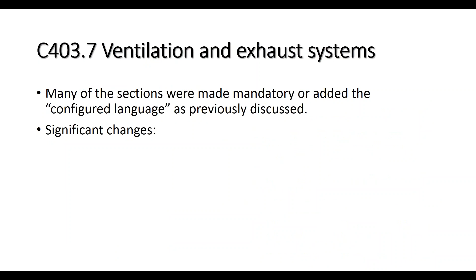Some of the significant changes that you'll find are in the ventilation. They went through and changed the language from capable to configured, and then added this thing that says, if you're bringing in some outdoor air and you're heating it, don't heat it to more than 60 degrees. If you're trying to cool the building, why are you tempering it? And then if there are energy recovery requirements in certain situations, this just added more climate zones to that. Climate zones 7 and 8 really never had energy recovery requirements, and now they've been added. Not saying that they're required in those climate zones, only under certain situations.